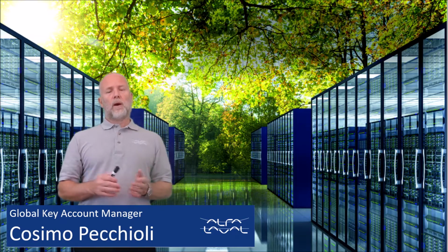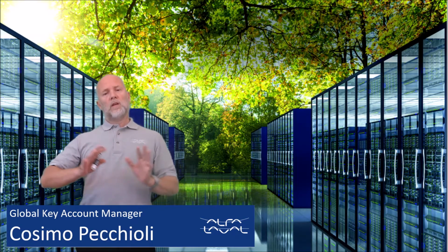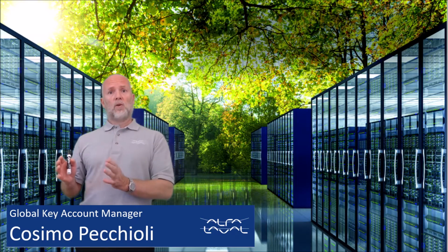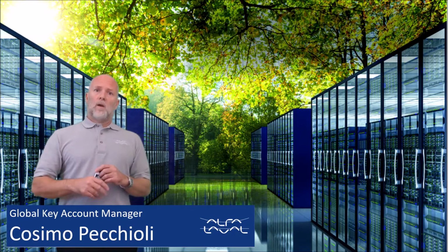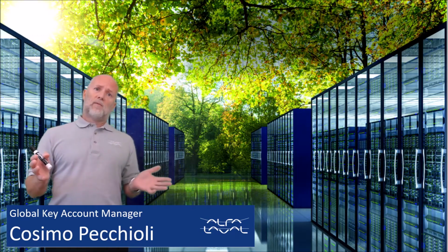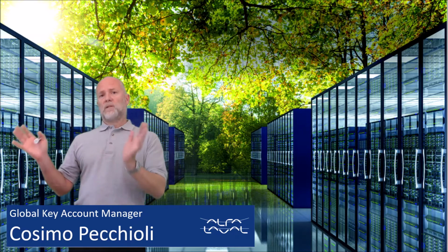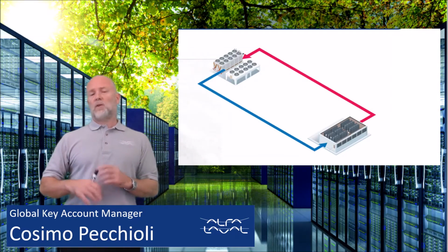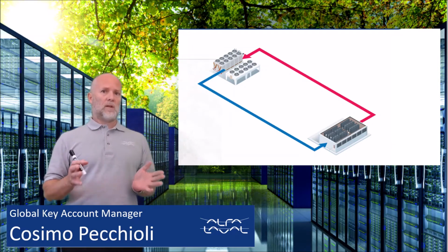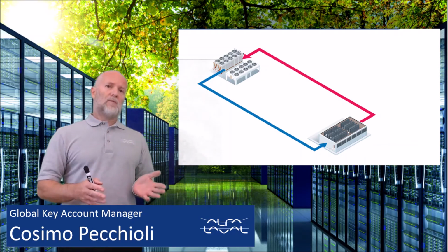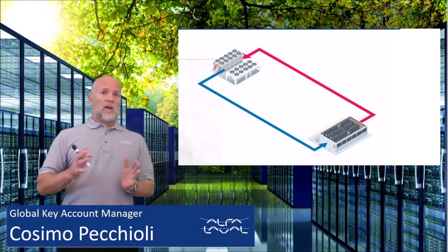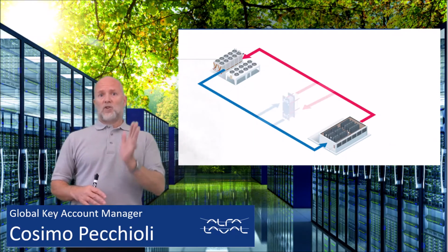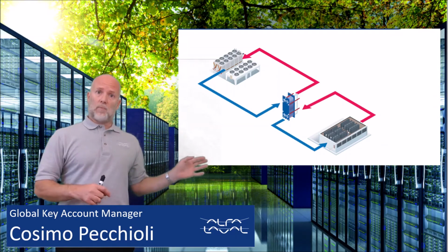Today we talk about whether it is advisable to decouple your cooling system if you have an evaporative cooling tower or if you have air coolers. The concept is that if you have an evaporative cooling tower, of course, you have an open system that is exposed to the elements and all the contaminants in the air. So in that case, it's not really a choice. It's absolutely advisable to put a heat exchanger between the external world and your server room that acts like a shield and protects your IT equipment.